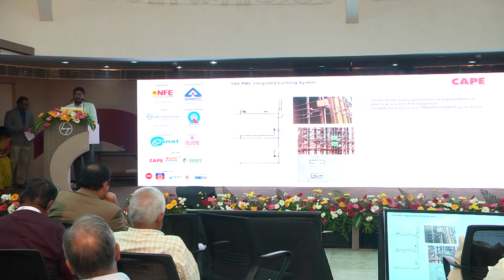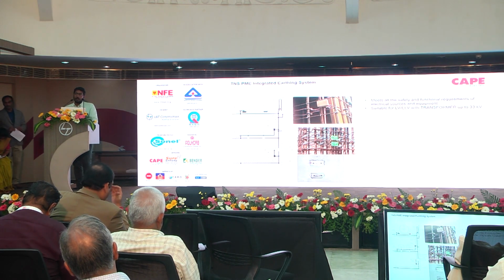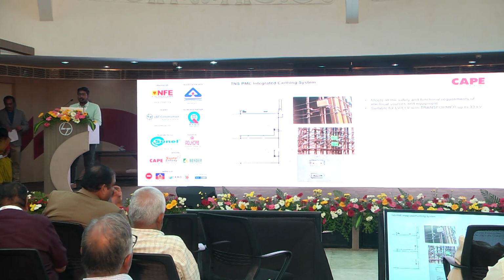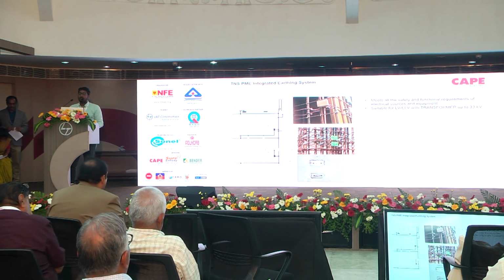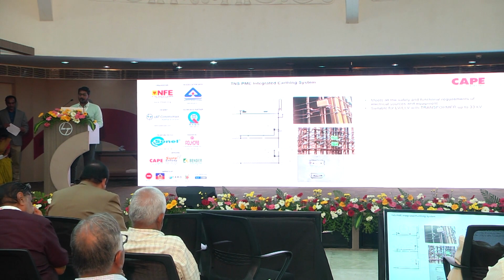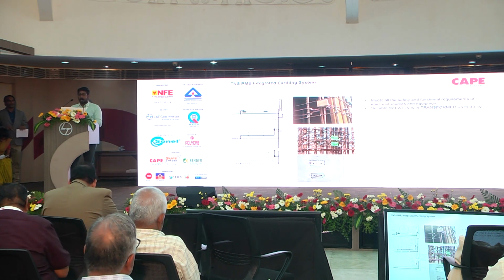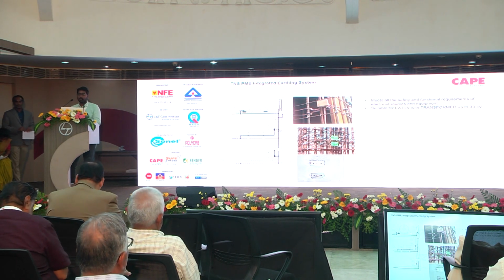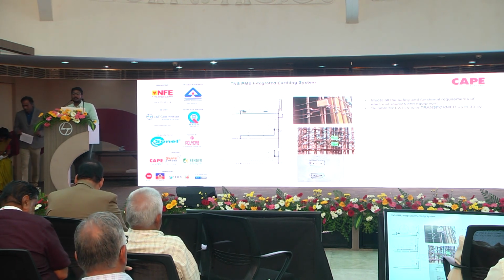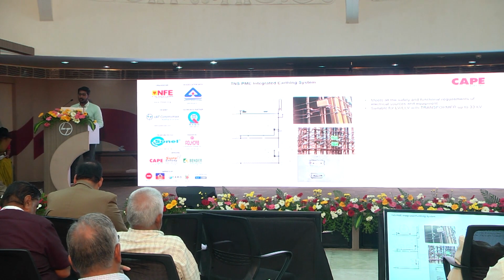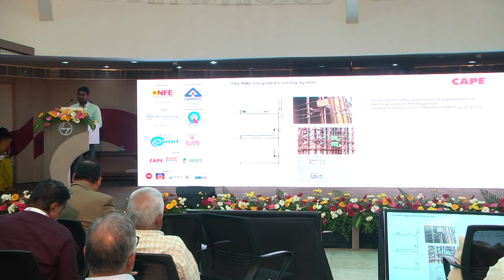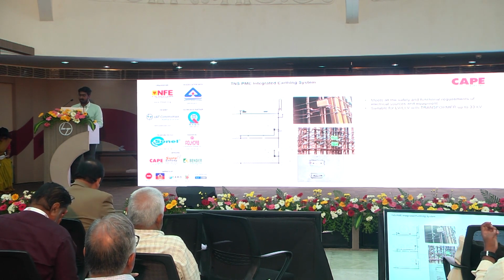We are adopting a TN-S network with protective multiple earthing. In this, we select the conductors and the earth stud, which we term as a MET, based upon the fault current rating. Based upon the fault current rating, the conductor selection, the grid size selection, everything will be done, and it is embedded along with the structure. So it will meet all the safety requirements and functional requirements of the electrical source and equipment, and it is suitable for LV and ELV transformer earthing up to 33 kV.